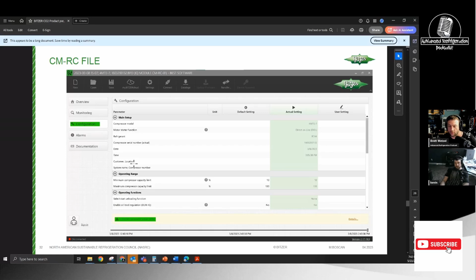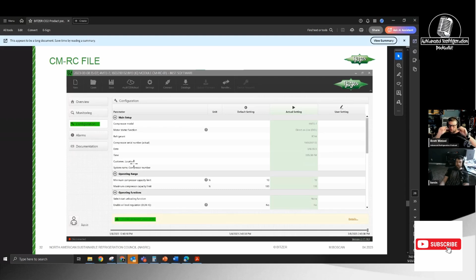Yeah, basically. But on this one, the one I was working on, I got rid of the DO for the Danfoss and basically was straight relying on the low pressure switch to make and break. Yeah, see, with these, all it does is get rid of the DO. The low pressure switch is still wired in series on the safety circuit, but it just gets rid of the DO.